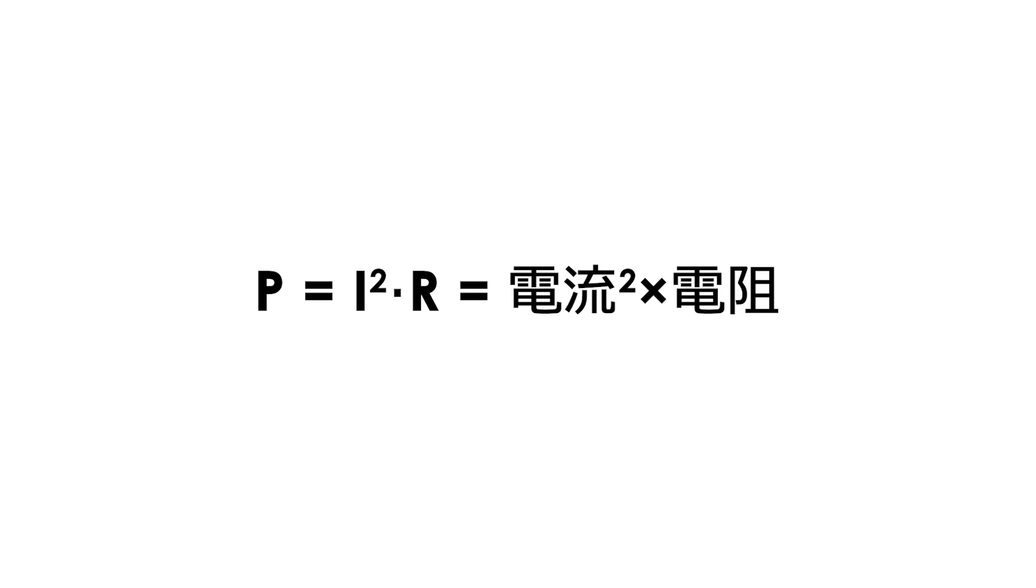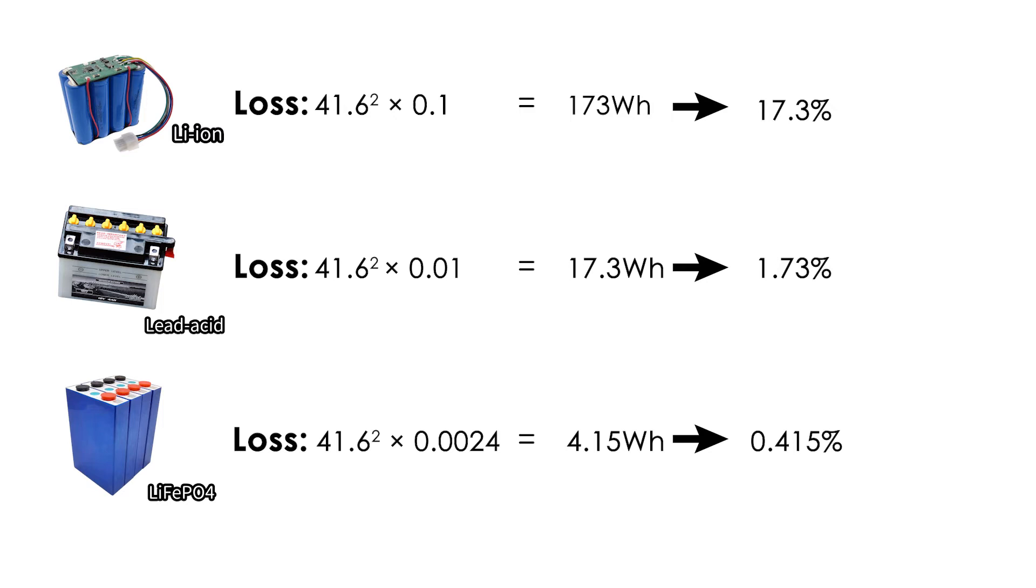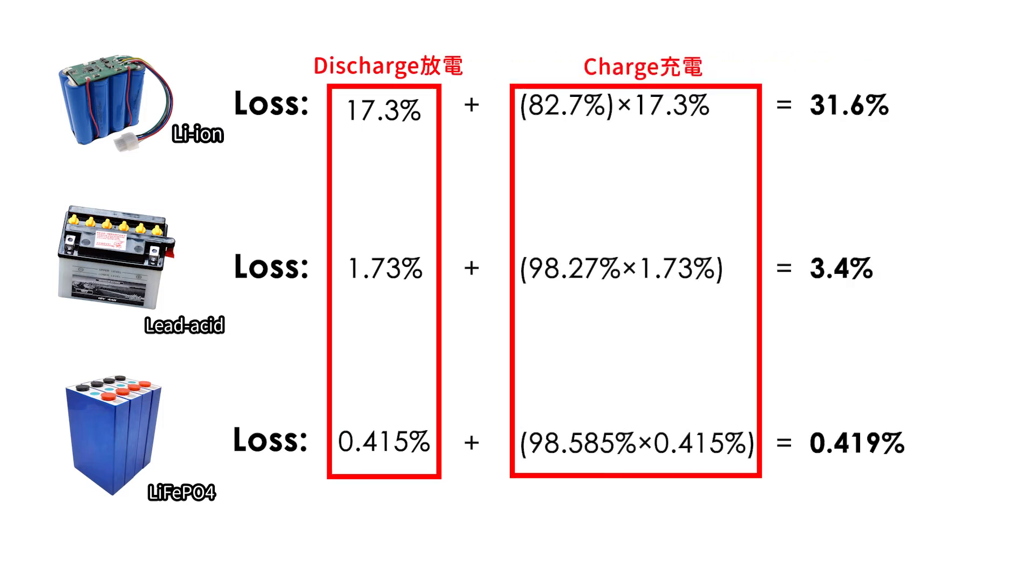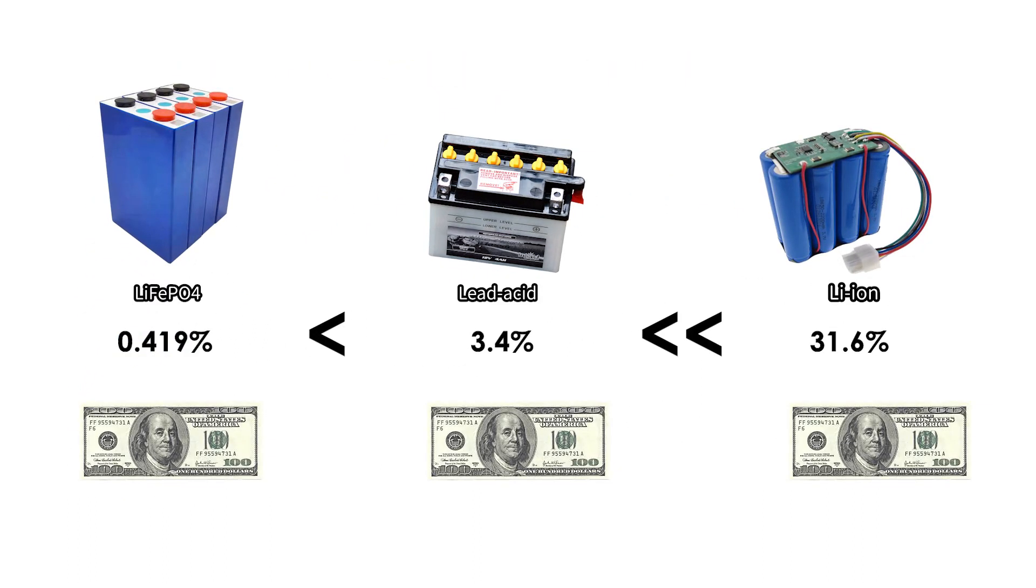The internal resistance loss of the lithium-ion battery is 173Wh, and the loss rate is 17.3%. The internal resistance loss of the lead-acid battery is 17.3Wh, and the loss rate is 1.73%. The internal resistance loss of the lithium iron phosphate battery is 4.15Wh, and the loss rate is 0.415%. Taking into account charging and discharging, the losses due to the internal resistance are doubled. So when choosing a battery, also take into account the difference in electricity bills due to internal resistance losses.